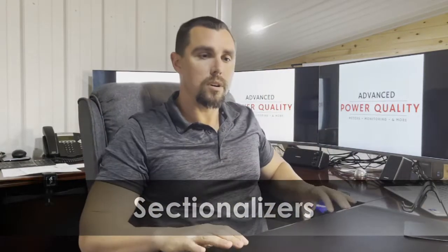Sectionalizers work off of a count system. Whenever they sense zero current, they do a count. This would work properly if you had a breaker at the substation, a recloser, and a sectionalizer downstream. The breaker trips, the recloser trips, and the sectionalizer counts. But whenever you have a solar farm backfeeding the system downstream, that sectionalizer will never count zero because it's sensing that backfeed. So your sectionalizers are essentially useless in that scenario.